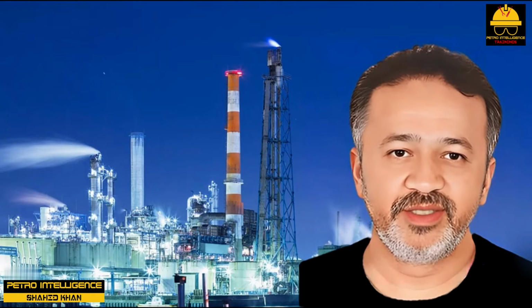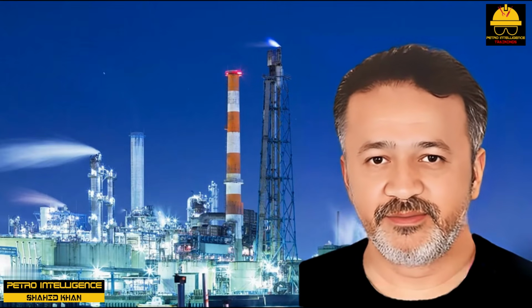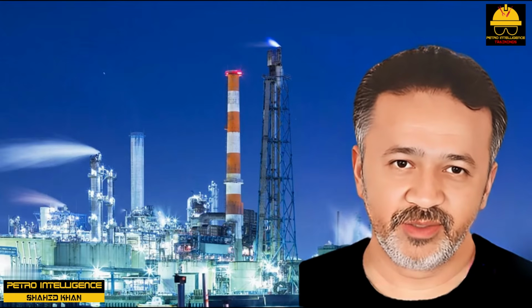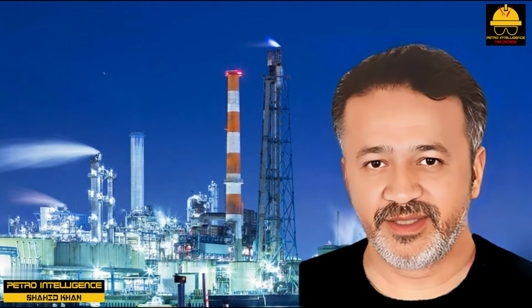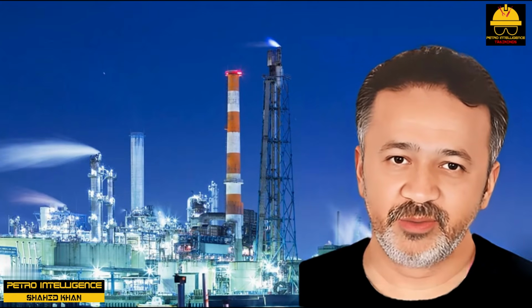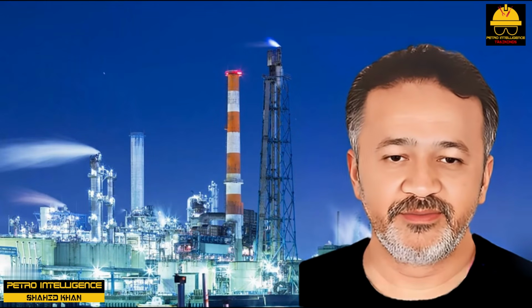Now let's assume that there is a refrigerant receiver between the condenser and letdown valve. This traps any uncondensed vapors. The accumulation of these vapors raises the pressure in the receiver. This puts back pressure on the condenser. The higher condenser pressure promotes more complete condensation of the refrigerant vapors.